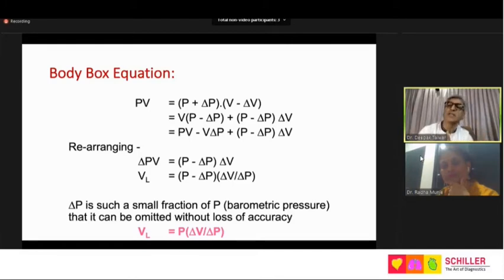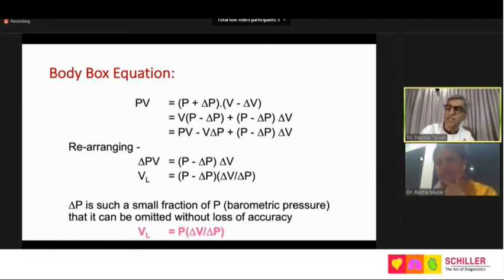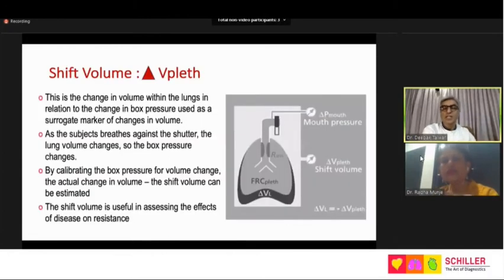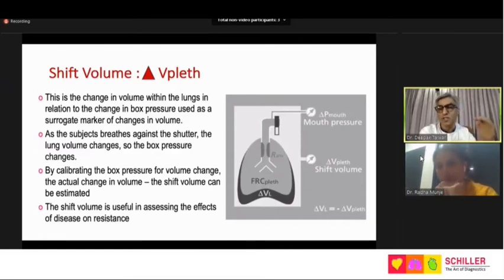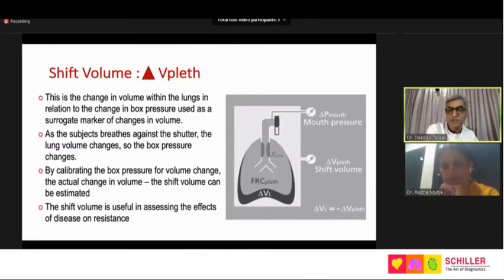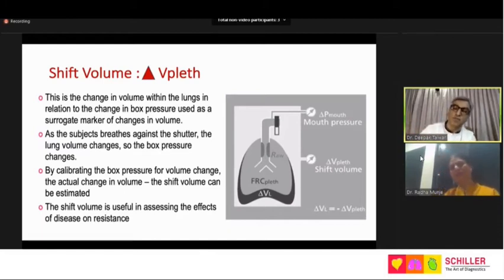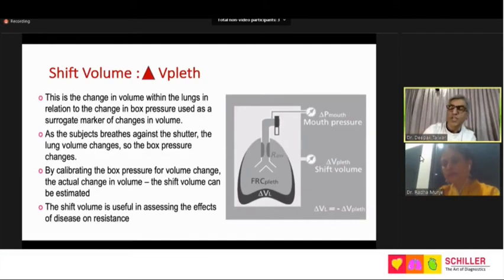Certain things are known and only the lung volume is unknown. With mouth pressure, box pressure, and box volume known, you rearrange the equation to calculate lung volume. During the procedure there is a volume shift between panting with the shutter open versus shutter closed. This shift is transmitted to the box, changing box pressure. From calibration we know how much pressure change corresponds to how much volume change — the volume shift measured by pressure changes in the box is the entire crux of body box plethysmography.